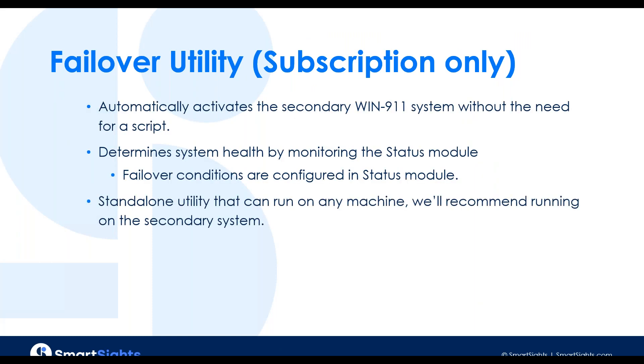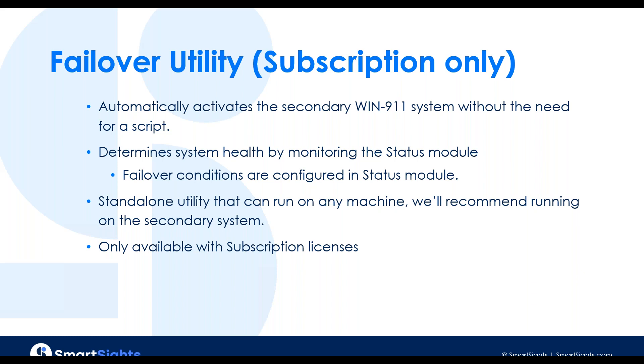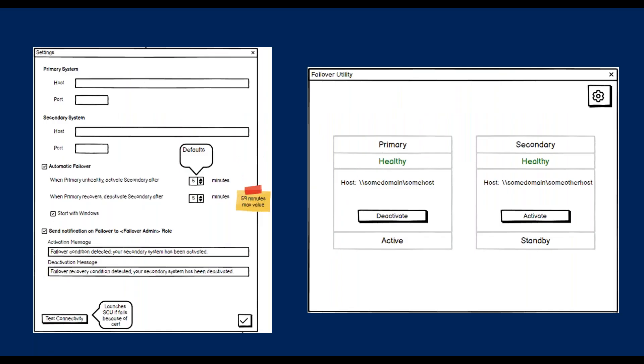The failover utility is designed so that if you have a primary and a secondary WIN-911 system and one of them goes down, this utility will be monitoring them and, depending on your configuration, will fail one system over to the other. If it recovers, it will fail it back over. We've been doing this before with scripts, and nobody really wants to deal with a script, so we finally built the utility to handle it automatically. It's a very simple utility — you point it at two different systems, choose a few options, and you're monitoring both. When they're in a bad state, they'll automatically fail over. All of this will be configurable within our status module.